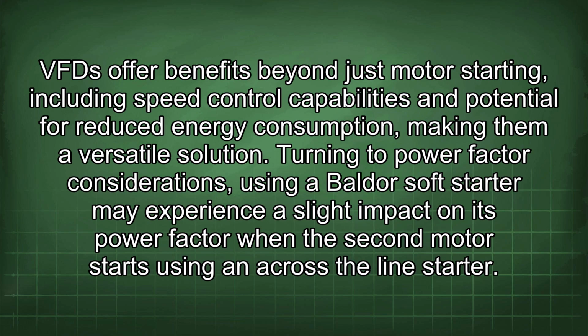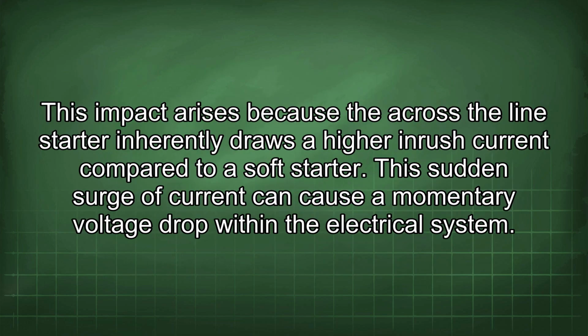Turning to power factor considerations, a motor using a soft starter may experience a slight impact on its power factor when the second motor starts using an across-the-line starter. This impact arises because the across-the-line starter inherently draws a higher inrush current compared to a soft starter. This sudden surge of current can cause a momentary voltage drop within the electrical system.